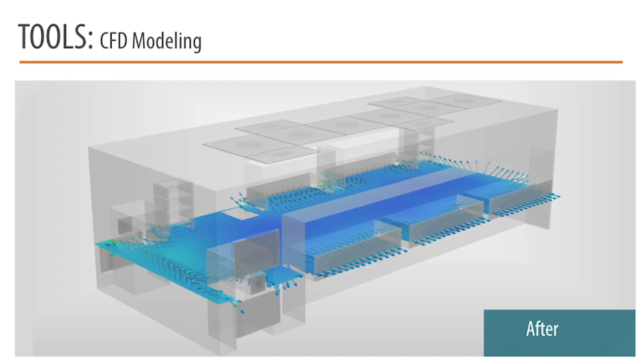How did we get there? These wet benches are big, massive open areas. The original program for this project was that the chemical work inside these benches would be piped to central chemical waste collection tanks. That was value engineered out, as was the fact that in that original scenario, the bottom piece of the bench didn't exist, and air could get under the bench and into the return grills. When the central systems got value engineered out, we ended up with containers underneath each bench collecting the chemicals, which effectively blocked off the air path to the return chase. That's why we got into this modeling, and we snuck return chases into every corner we could find in the room, and got it to pass certification.